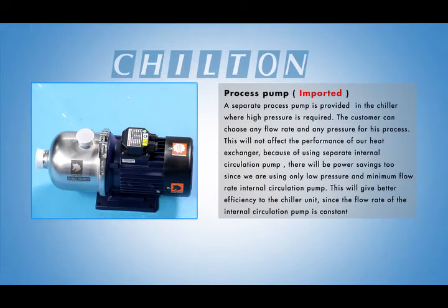Process pump. A separate process pump is provided in the chiller where high pressure is required. The customer can choose any flow rate and any pressure for his process. This will not affect the performance of our heat exchanger. Because of using a separate internal circulation pump, there will be power savings too, since we are using only a low pressure and minimum flow rate internal circulation pump. This will give better efficiency to the chiller unit since the flow rate of the internal circulation pump is constant.